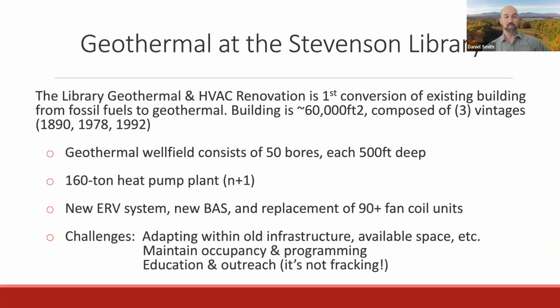So a bit about the project, the library: this was our first conversion of an existing building. We have a lot of geothermal on campus, but those were all new construction at their time of completion, so this is the first conversion of an existing building from fossil fuels to geothermal. It's a roughly 60,000 square foot building composed of three vintages: 1890, 1978, and 1992. The geothermal well field consists of 50 boreholes, each 500 feet deep. We replaced a 160-ton heat pump plant, which gives us N+1 redundancy - if ever we lose one heat pump, we're still good.